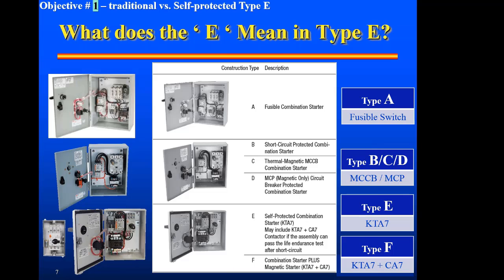Well, from an electrical control construction standards or construction identification, there's a letter code that I've got on the screen, A through F, from an electrical control letter code, not to confuse or mix up with a motor design criteria. That's a different category. But from a construction perspective, they say a Type A combo starter is something that's inclusive with a fusible switch. Type B is something that's going to be inclusive, that's going to have short circuit protection. Type C and D are the circuit breaker type of a combo starter, circuit breaker plus a contactor plus an overload. That's what Type C and D is.